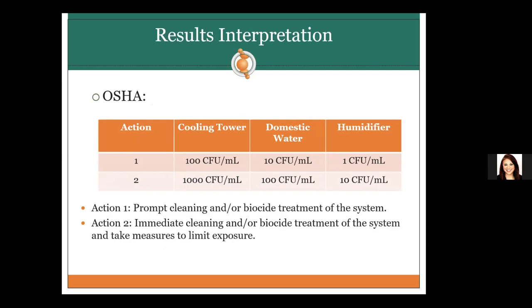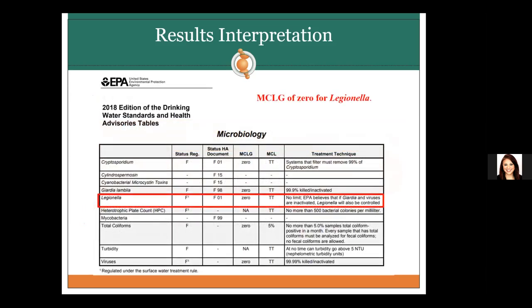After getting test results, how do you interpret them? OSHA has a recommendation table with two action levels. Action level one is prompt cleaning and biocide treatment of the system. Action level two is immediate cleaning or biocide treatment. When you have a higher bacterial load, you want to act quickly. EPA also has guidelines, with zero as the maximum contaminant level goal.